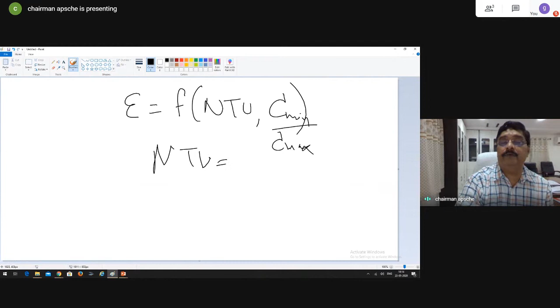And how do you calculate effectiveness? Effectiveness is given as a function of NTU and C, where C is C minimum divided by C maximum, the ratio of C minimum to C maximum. What is NTU? NTU comes up in the derivations when you solve for the effectiveness, and in heat transfer parlance, NTU is equated to UA by C minimum. What is U? The overall heat transfer coefficient, and A of course is the surface area.